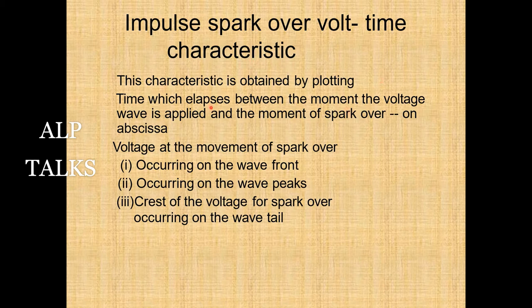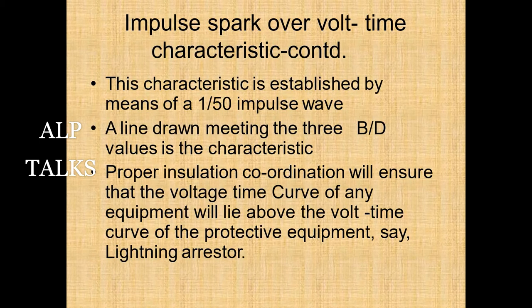The impulse spark overvoltage-time characteristic is obtained by plotting the time elapsed between the moment the voltage wave is applied and the moment of sparkover — including sparkover on the wave front, at the wave crest, and on the wave tail. This characteristic is established by means of a 1/50 impulse wave. Proper insulation coordination ensures that the voltage-time curve of any equipment lies above the voltage-time curve of the protective equipment, i.e., the lightning arrester.